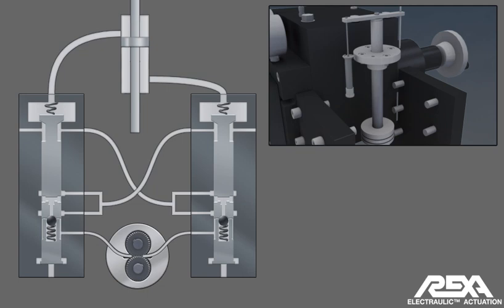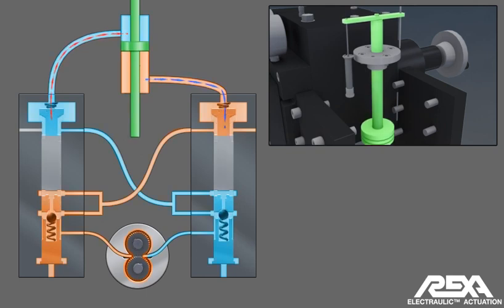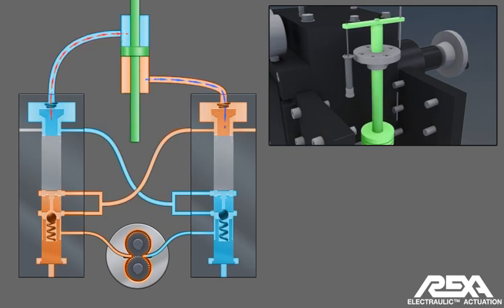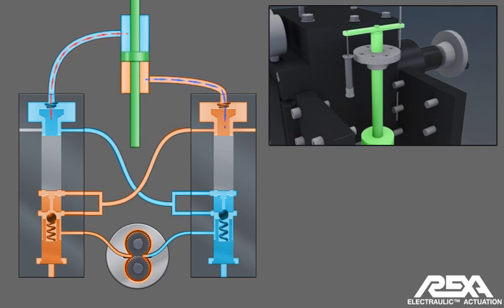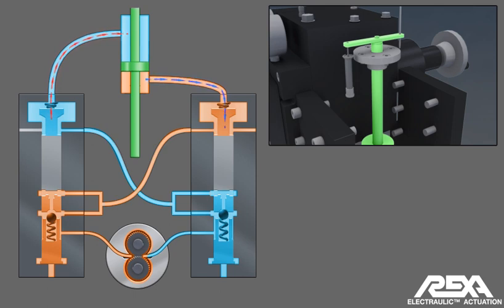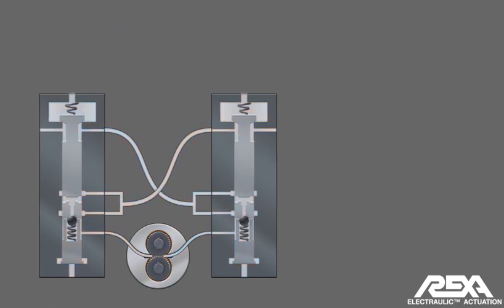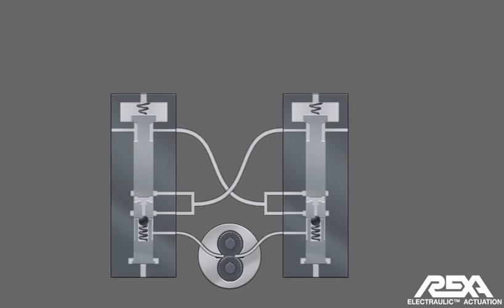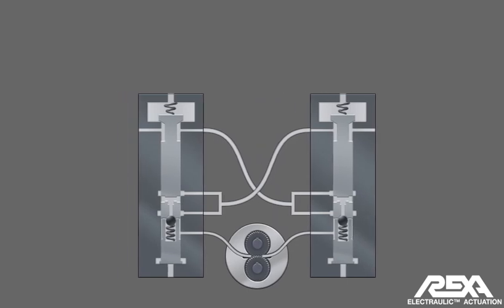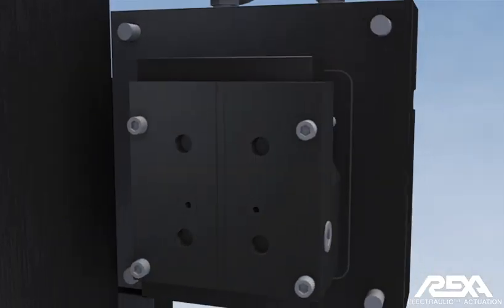If the valve was required to move in the other direction, the pump motor will start in the reverse direction, causing the flow circuit to reverse in the mirror image. The actuator will move the connected valve in the opposite direction. Once the valve reaches the desired position, the pump will stop, the flow match valves will return to their normal position, and the valve actuator will be locked in its current position.